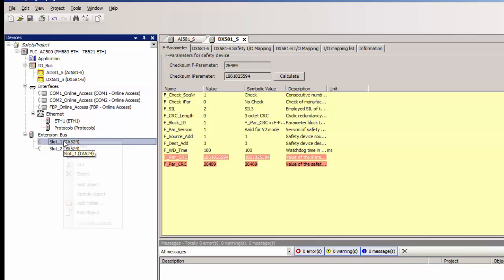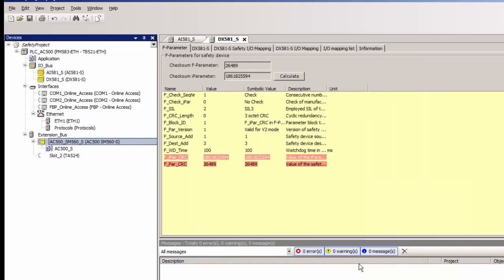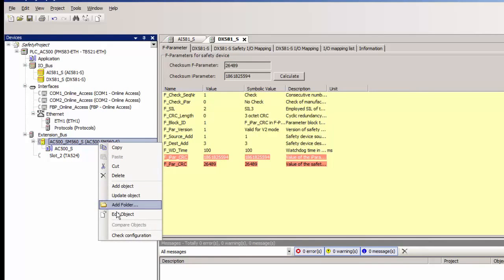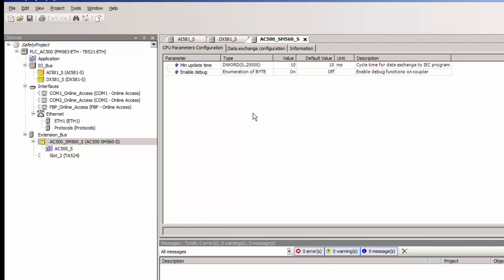Now we add the safety CPU SM560S in the extension bus slot as per the physical placement. We need to set the enable debug parameter to on, so that the non-safety CPU will have access right to transfer the safety project to the safety CPU.